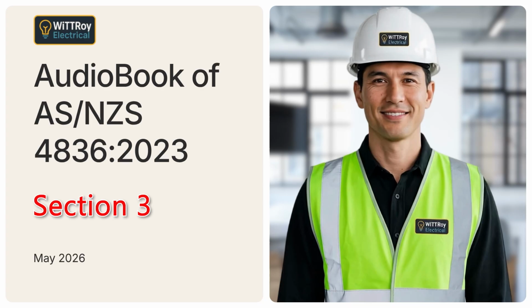If work is left unfinished, the workplace must be left in a safe state for other people. Electrical equipment must be returned to service in its original state. If that is not possible, a competent person must assess any changes made to the equipment. After electrical testing of cables, a considerable capacitive charge may remain on the cable. Those cables must be properly discharged to earth before handling. This removes the stored capacitive charge.